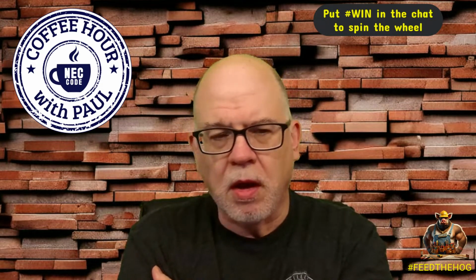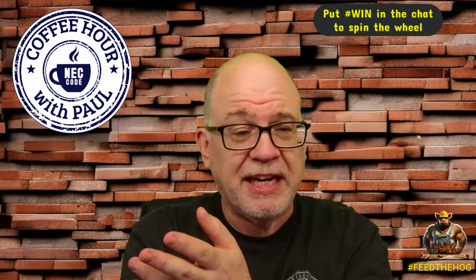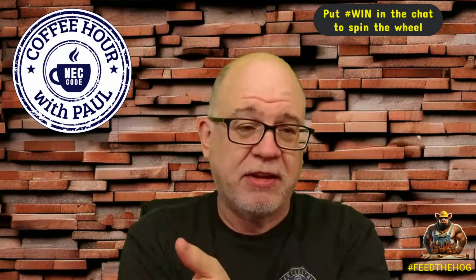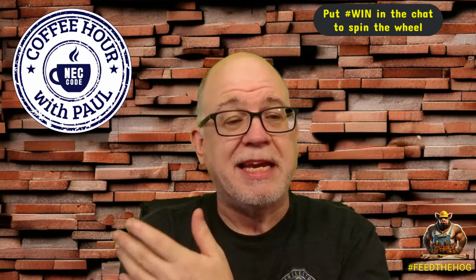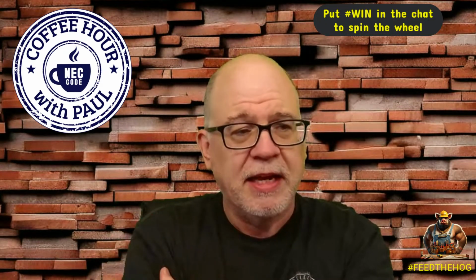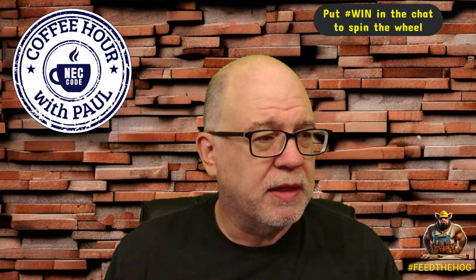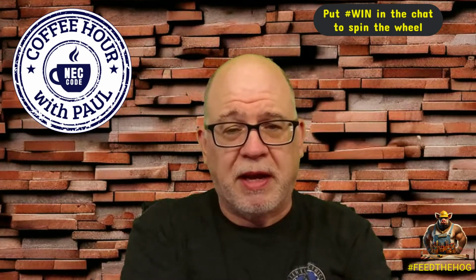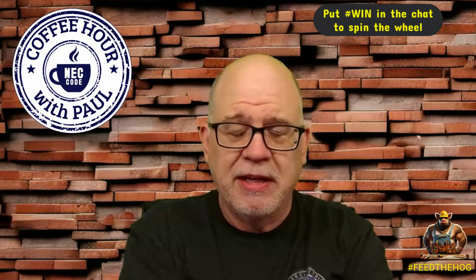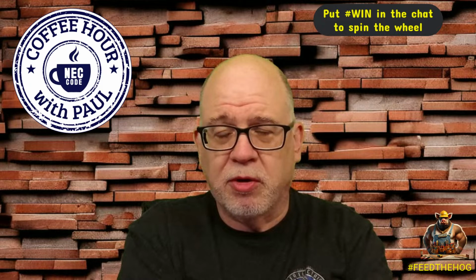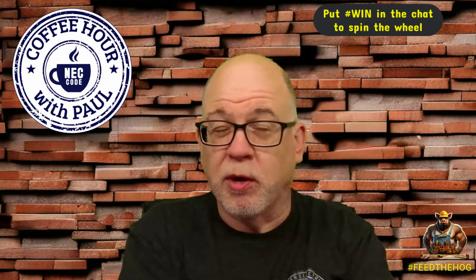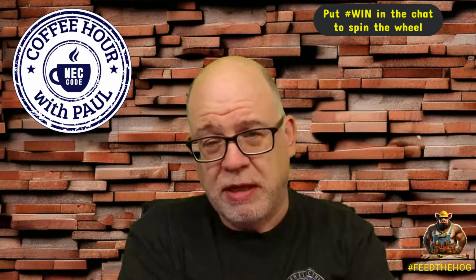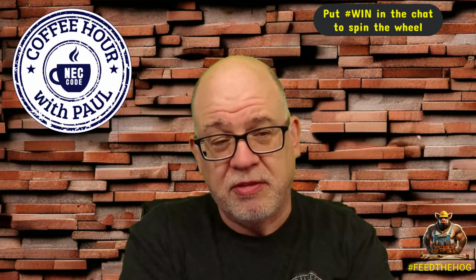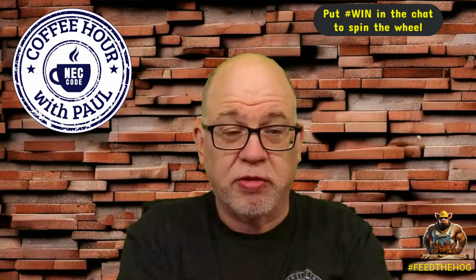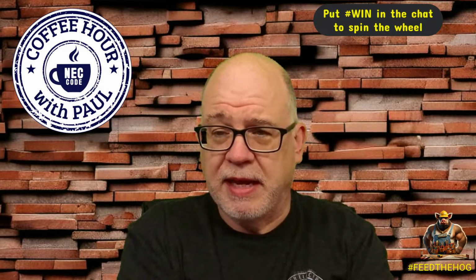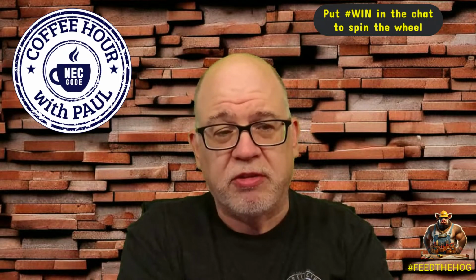Now, we had a question yesterday that I didn't answer because it was right at the end of the show. I emailed the individual directly and was able to answer that question. Their question was: if you had a multifamily building with lighting that is 277/480, would you be able to apply 310.12, the 83%, or is there anywhere else in the code that would allow you to do that? The answer is no. 310.12 is very specific to dwelling units. So you would take the commercial area and treat it just like a commercial area, and use Part 3 as normal for that.